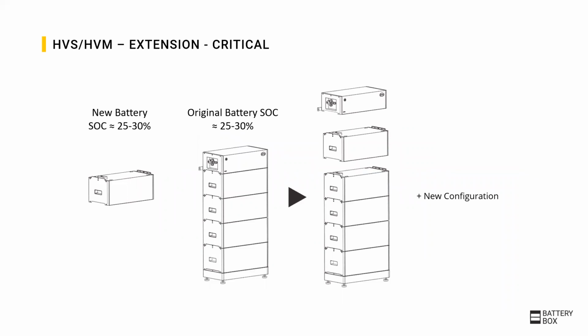If the battery should be extended later or a module is exchanged, it is very important to have a similar state of charge in all modules. As new modules arrive with about 25 to 30% state of charge, the original battery should be turned off at about the same SoC. Then the new module can simply be added. After this, the configuration has to be done again with the new module quantity.